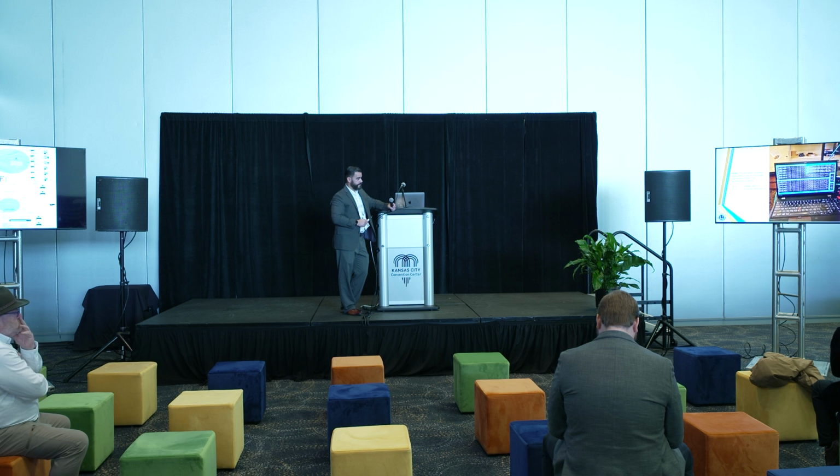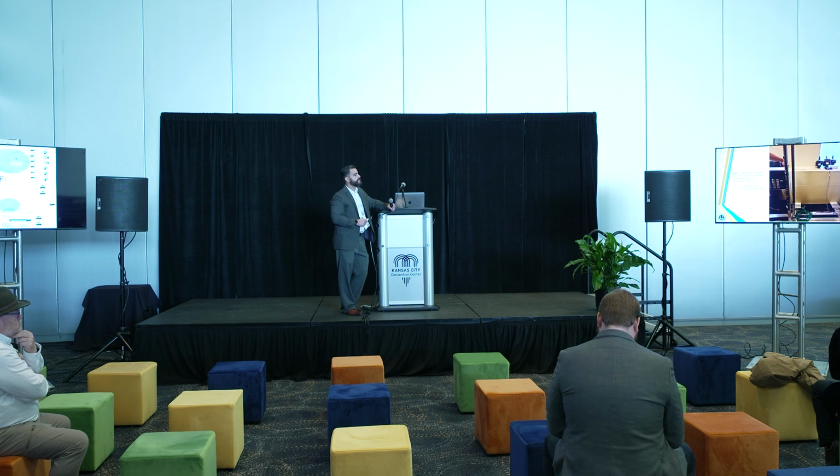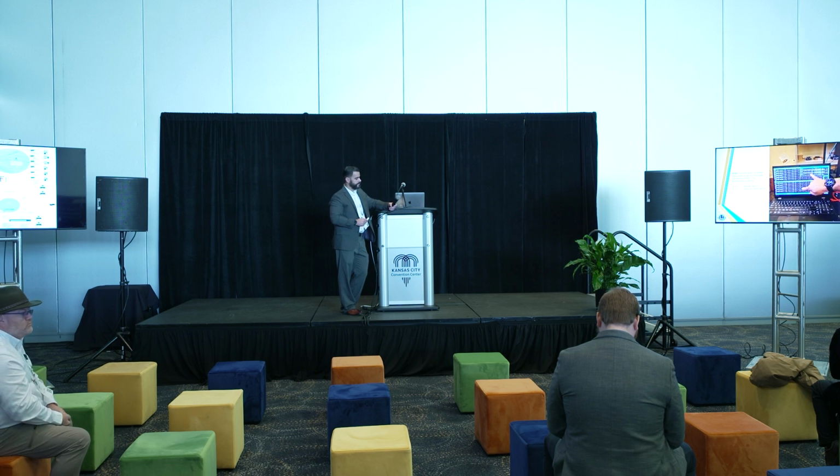And now we're going to perform a second failure, and this time instead of cellular, we're going to fail physically at the Hub 1 location. So Clayton is going to yank the cable between the LAN device of the Aprisa router and the SEL box. All right, cable's been pulled. Same as before, last poll we see is 10.10 reaching out, and that is it. There's no more conversation going on because the LAN cable has been severed, but note that we still have a conversation between Hub 2's router and LAN polling device to spoke 1's SEL box as well.